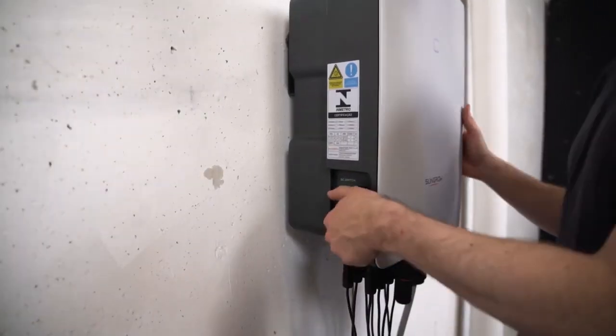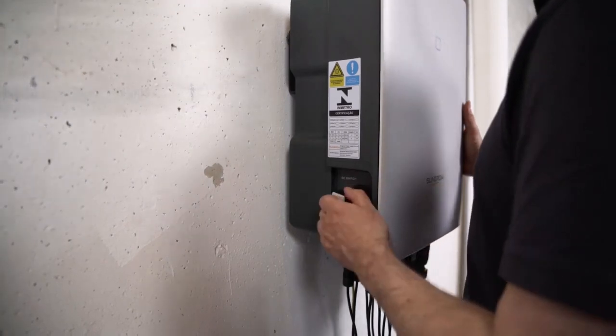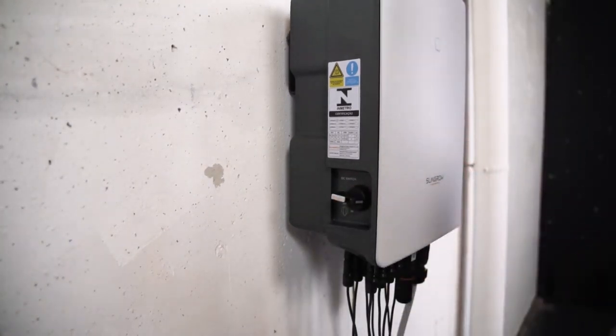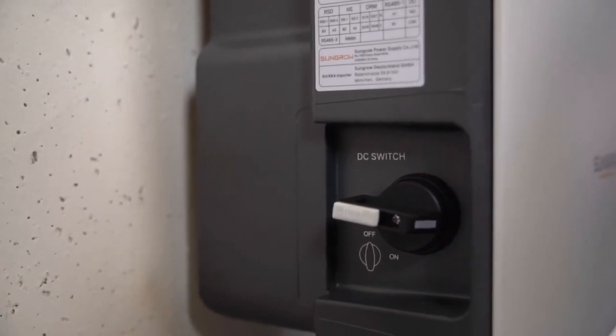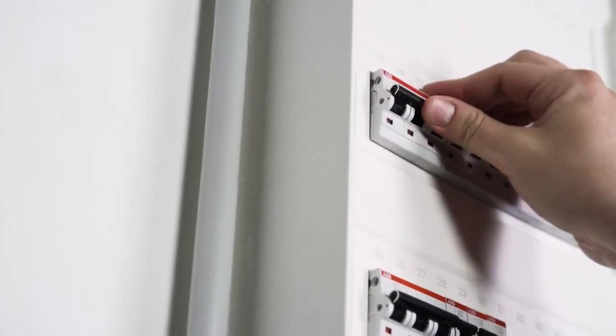Now it's time for commissioning. First, you have to set the DC switch of the inverter to the on position to connect the inverter to the PV generator. Next, you have to switch on the AC circuit breaker. A look at the LED light tells you if everything works properly. If the light shines continuously blue, the inverter is ready for use. If this is not the case, please refer to the manual where you will find a breakdown of the different light signals.